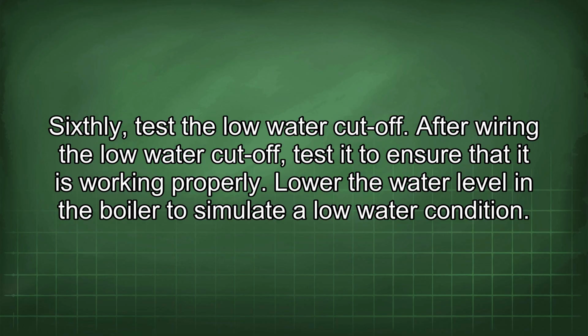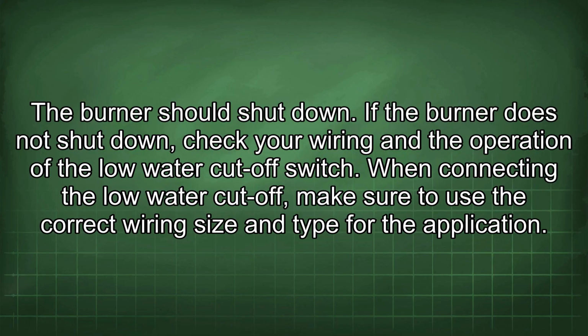After wiring the low water cutoff, test it to ensure that it is working properly. Lower the water level in the boiler to simulate a low water condition. The burner should shut down. If the burner does not shut down, check your wiring and the operation of the low water cutoff switch.